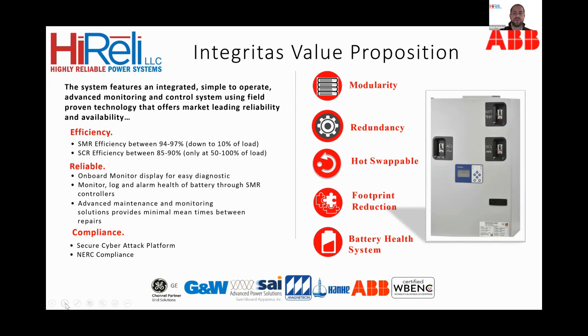Some of the Integritas value propositions as to why the ABB battery chargers are an industry-leading design. These products all offer high efficiency with high reliability while not compromising on the security of your system, with the secure cyber platform and NERC compliance. The modularity allows for growth of your system, which gives you multiple rectifier modules per unit. As for redundancy, you can add rectifiers to your system giving you N+1 redundancy. The rectifiers are hot swappable, so they can be field upgraded or replaced while still online without disrupting your load. There is a reduction in footprint, so this technology can provide higher current ampacities in a reduced footprint. And the battery health system is an integrated, simple to operate and advanced monitoring and control system. You can see on the front panel, you have the advanced controller.